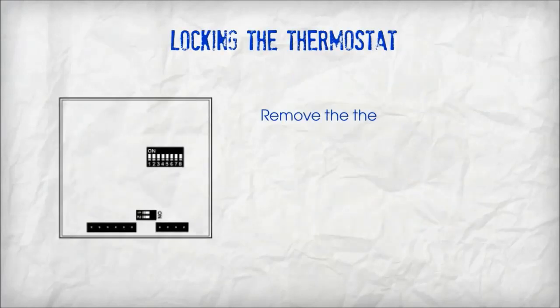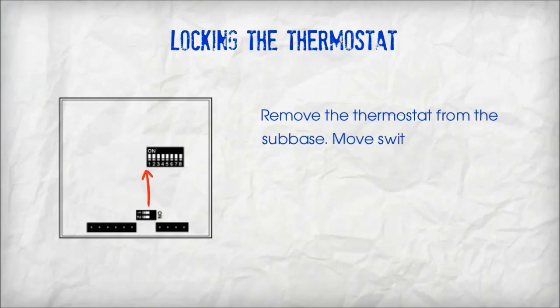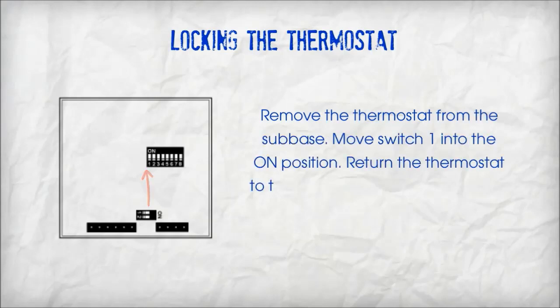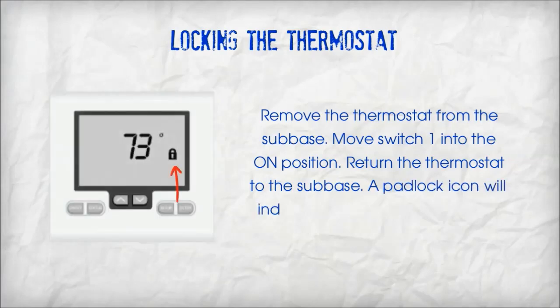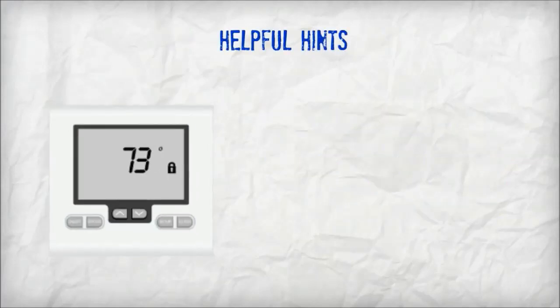To lock the thermostat, remove the thermostat from the subbase. Move switch 1 into the on position, then return the thermostat to the subbase. A padlock icon will indicate the thermostat is locked.